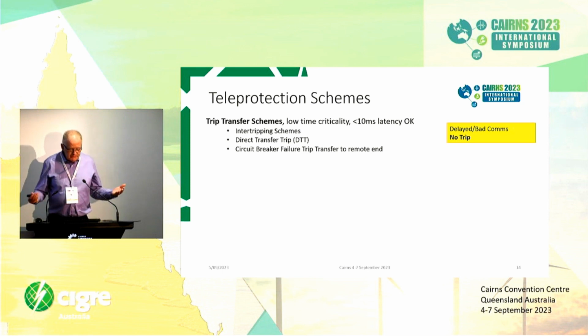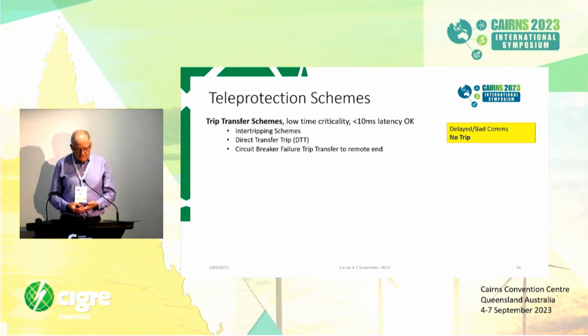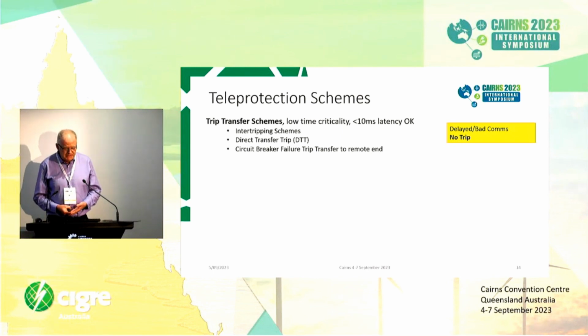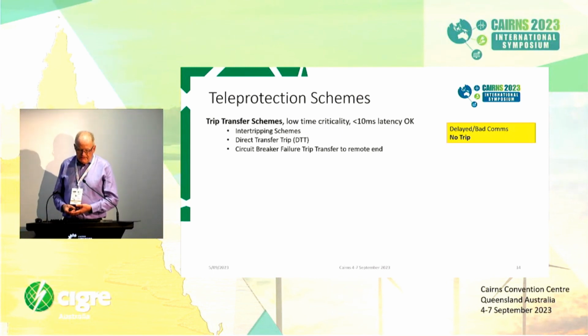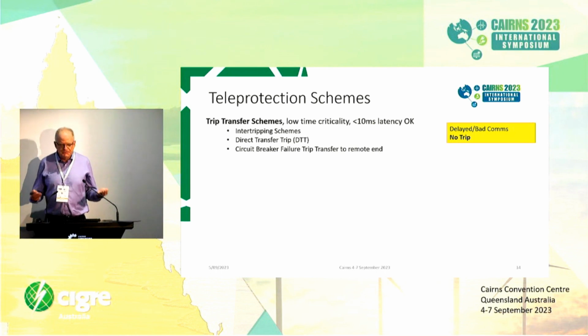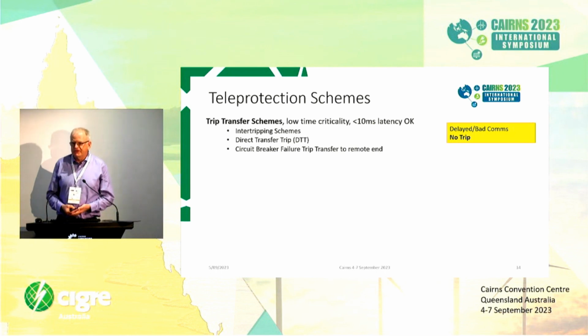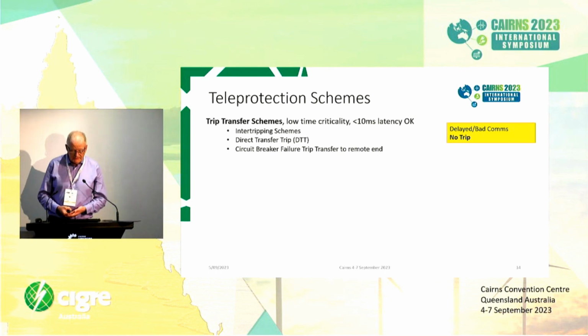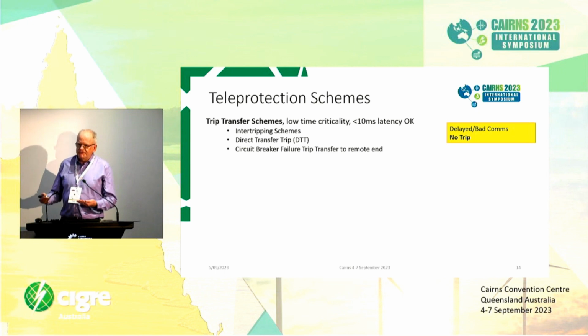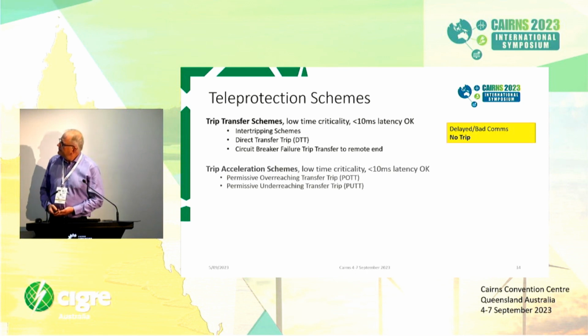So, like I said, low time criticality, not particularly latency intensive. If the trip does get delayed, it really results in non-tripping of the line, which from a protection perspective isn't great. We want to make sure the line's protected, but there is backup protection, obviously. The important thing is it's kind of fail-safe, so any issues with the communications, you're not going to start tripping your transmission network.